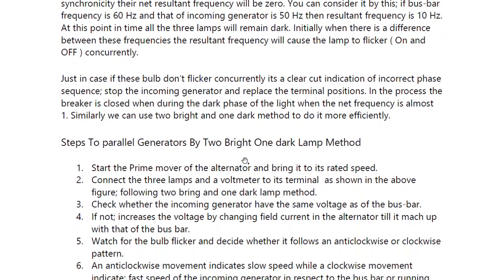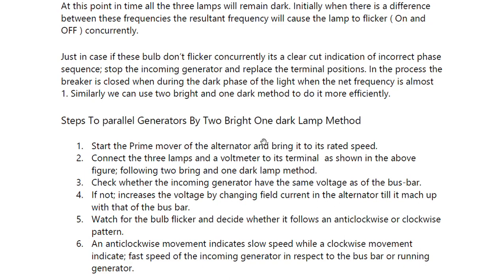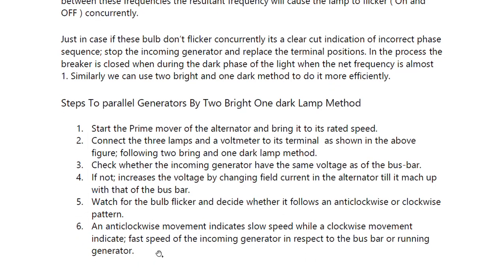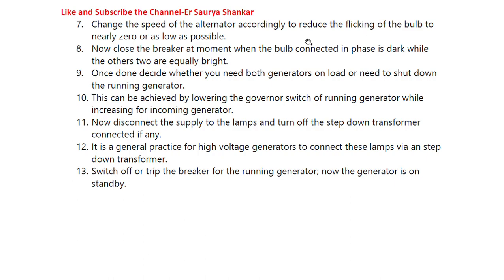Steps to parallel a generator using the two bright one dark lamp method: start the prime mover of the alternator and bring it to rated speed. Connect the three lamps and voltmeter to the terminals as per the two bright one dark lamp method. Check whether the incoming generator has the same voltage as the bus bar — if not, increase the voltage by changing the field current in the alternator until it matches. Watch for the bulb flickering and determine whether it follows an anti-clockwise or clockwise pattern. Anti-clockwise movement indicates slow speed while clockwise indicates fast speed of the incoming generator relative to the bus bar. Change the speed of the alternator accordingly to reduce the flickering to nearly zero.